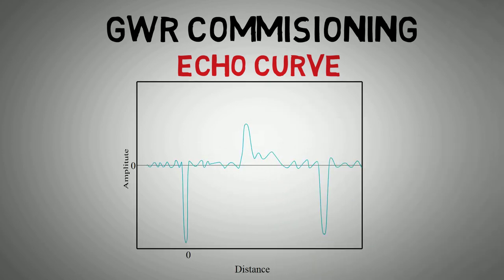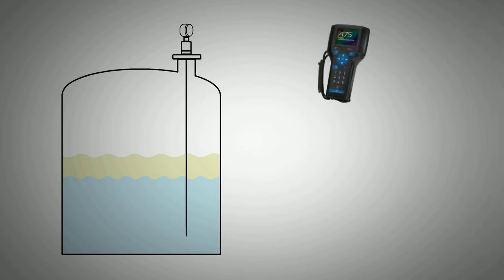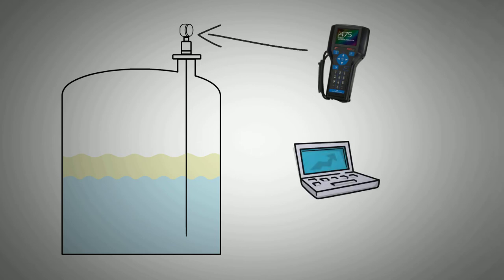The echo curve is a visual graph form representation of the microwave reflection strength plotted over time. The echo curve is usually viewed via a connected communicator such as a HART 475. Alternatively, some manufacturers use a laptop with proprietary software installed during commissioning or fault finding.